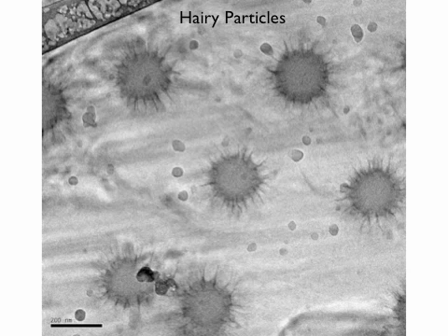We freeze it in liquid ethane, because now the ice has to be amorphous, because you go all the way through the sample. So if the ice is crystalline, the electron beam will scatter, and you won't see anything. So we have to freeze so fast that we freeze faster than the ice can crystallize, so that's why we use liquid ethane. And typically you have to stay below minus 135 degrees Celsius, because that's the glass transition temperature of water ice. So below there, you end up with amorphous ice.